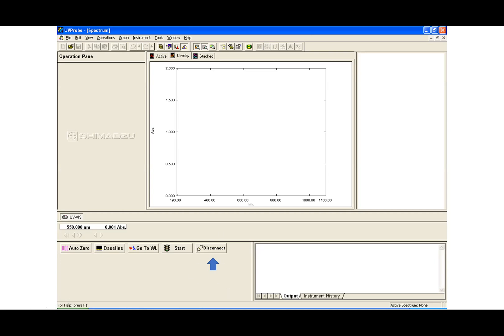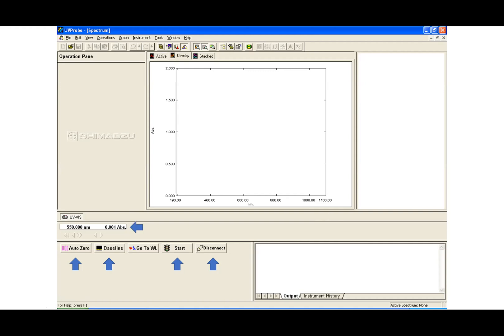Once you have the reference sample and the cuvette as well as the sample, both of them being blank, then you would want to auto zero the instrument and then click on Baseline. It also shows you a window where you can set the wavelength range that you're interested in, so normally I go from 190 to 1100 and then you just click Start. This window shows the absorbance real-time as you scan the sample.